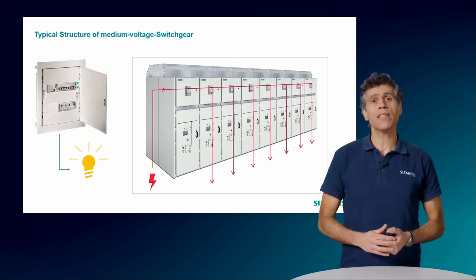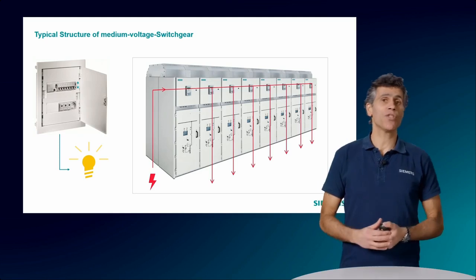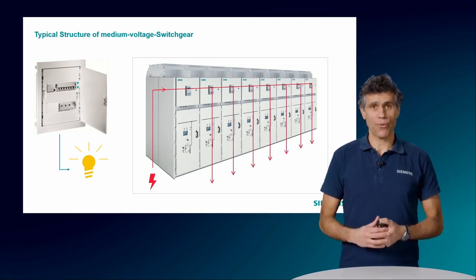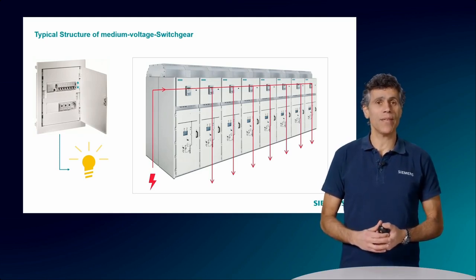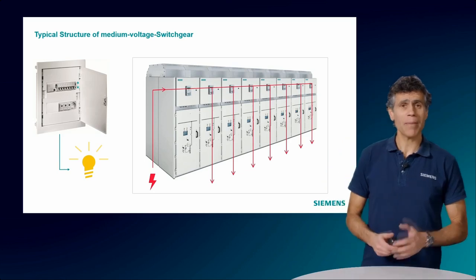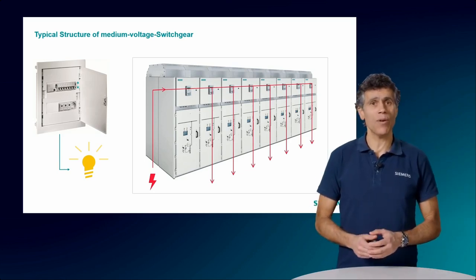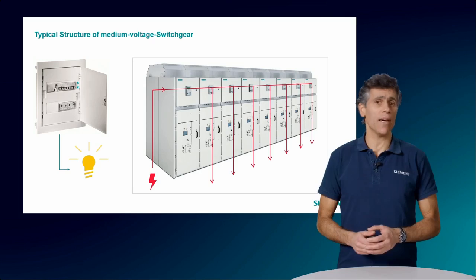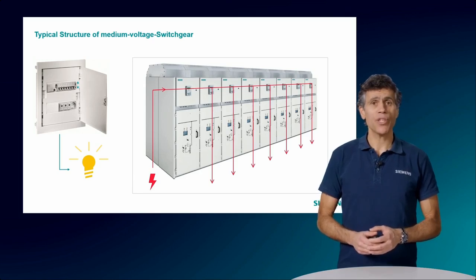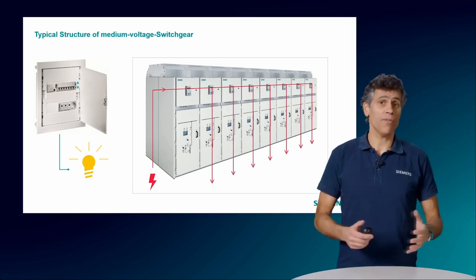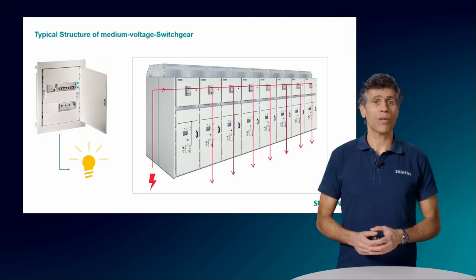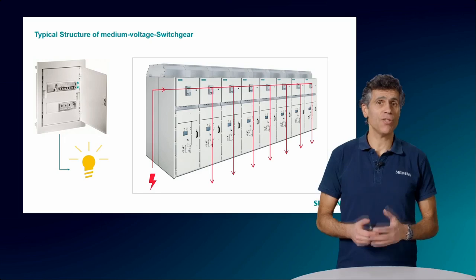The main difference between that and the medium voltage switchgear is that we usually have 3 phases instead of just 1 phase, and the power involved may be up to a few thousand times higher than at home. But let's disregard these details for now, as you will learn more about that in other units. A switchgear has an incomer panel, or several, that are connected to the network where the power is available. This is the entry of the energy to the switchgear.